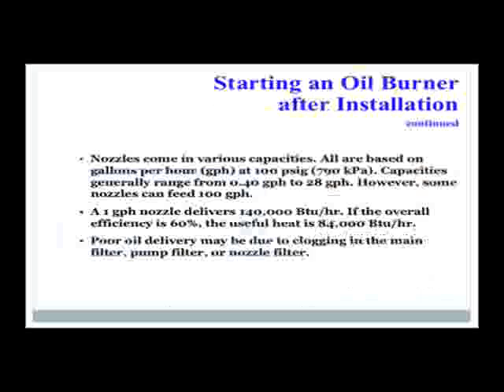Nozzles come in various capacities. All are based in gallons per hour at 100 psi. Capacities generally range from 0.4 to 28 GPH. However, some nozzles can feed 100 GPH. A 1 GPH nozzle delivers 140,000 BTUs per hour. If the overall efficiency is 60%, the useful heat is 84,000 BTUs per hour.